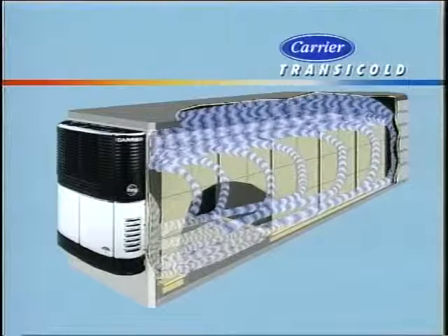The colder the engine is, the longer you will have to glow it. However, you never have to preheat the engine for more than 45 seconds. When the engine is preheated, place the manual glow crank switch into the crank position until the engine starts. Regardless of whether you start the unit automatically or manually, the unit is always turned off by simply placing the start run-off switch into the off position.